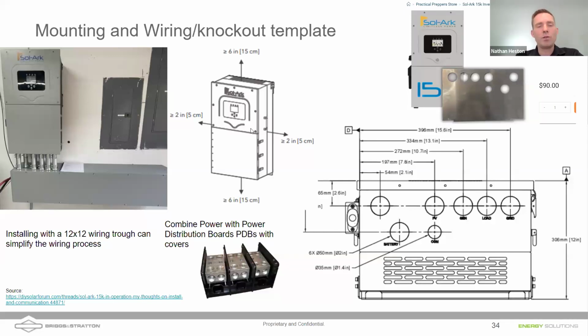The cooling fans on this unit are on the bottom and they blow that air up through the top. So there's only 2 inches of clearance needed on the sides. So you can put these inverters fairly close to each other, but you do need to give that 6-inch clearance on the bottom.